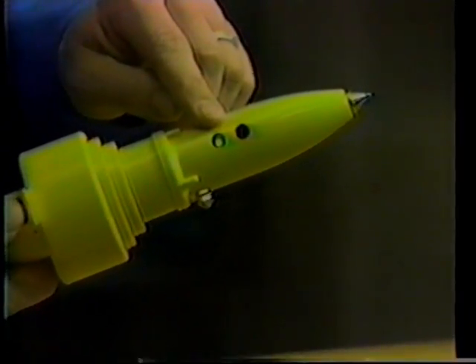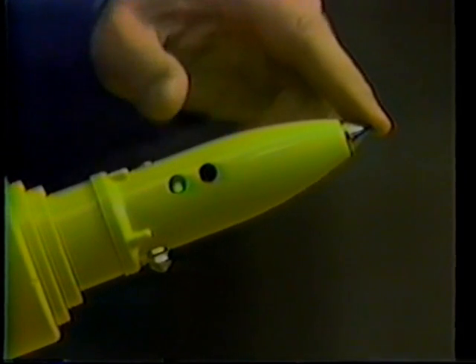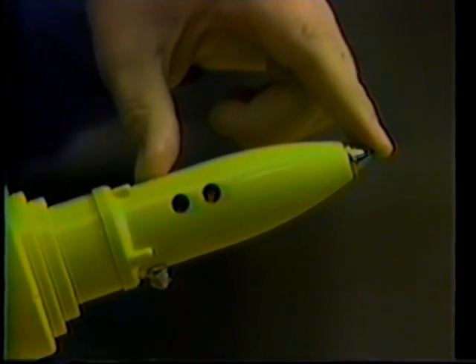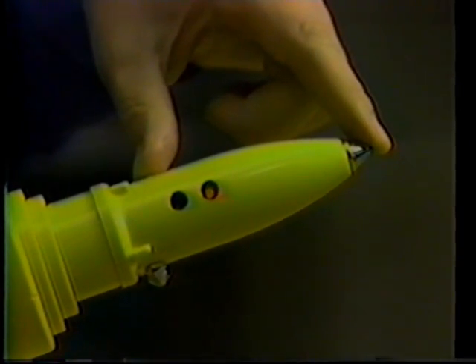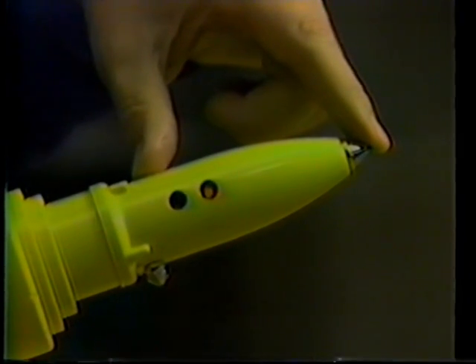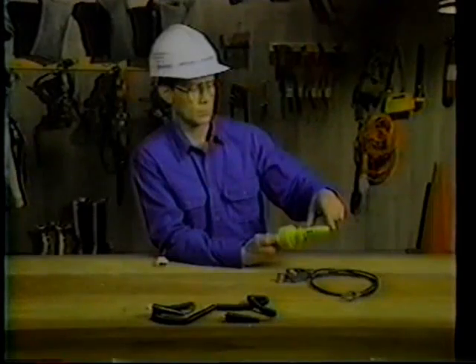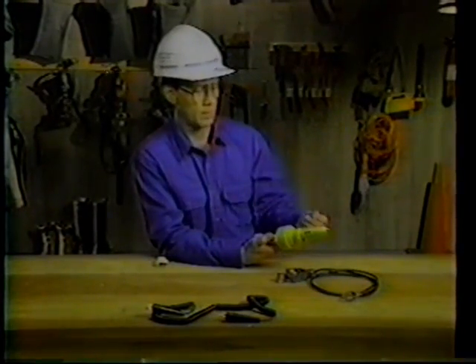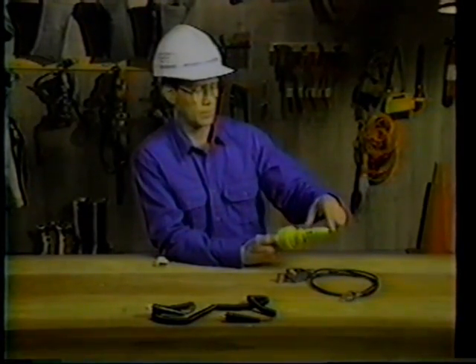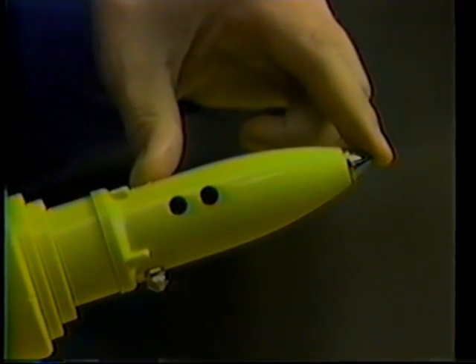When the green light glows, take your free hand and touch both the probe tip and the check contact screw at the same time, while keeping the switch depressed. The red light should flash. If the red light does not flash, do not use the 188A. One note, in very dry weather, you may have to moisten your fingers to perform this test.